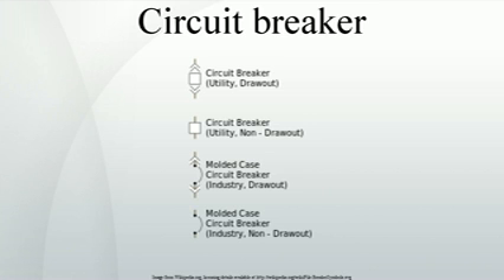Common trip breakers. When supplying a branch circuit with more than one live conductor, each live conductor must be protected by a breaker pole. To ensure that all live conductors are interrupted when any pole trips, a common trip breaker must be used. These may either contain 2 or 3 tripping mechanisms within one case, or for small breakers, may externally tie the poles together via their operating handles.